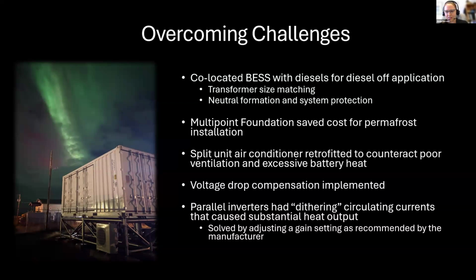One specific example of a set point changed according to a manufacturer recommendation: we had way more current on a bank of paralleled grid forming inverters than we expected, and there was basically a lot of circulating current going around.